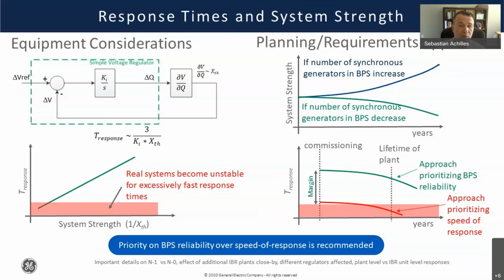If, on the contrary, at the time of commissioning you try to make your controllers as fast as possible so that they are stable but as fast as possible, then most likely what you'll experience is what's indicated with the red line: in a few years you're going to have to review these settings because this is going to start oscillating.